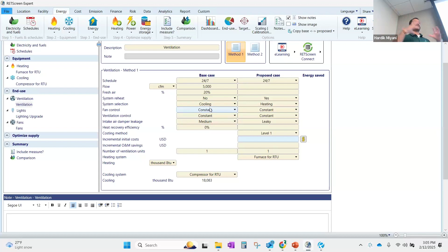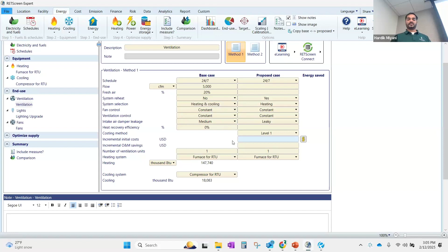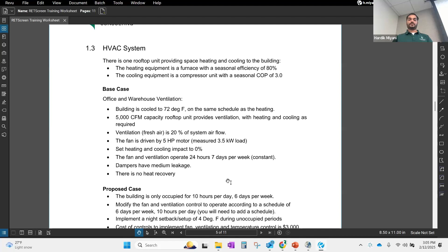Any questions on how to set up an HVAC system? Suppose you have a makeup air unit. A makeup air unit is something that brings in 100% outside air. So in that case, my fresh air will be 100%. Right? Same with the DOAS system. If you have a DOAS system with a heat recovery wheel, that is a place I will have my heat recovery efficiency. Right? If you have a terminal unit with reheat, that is a place I will set my system to be yes. If you have an HVAC system that is providing only cooling, right? In that case, I will select only cooling, right? So there are multiple ways you can set up depending upon how the design is for your property, right? So this is my base load energy consumption that I have set based on the information provided.